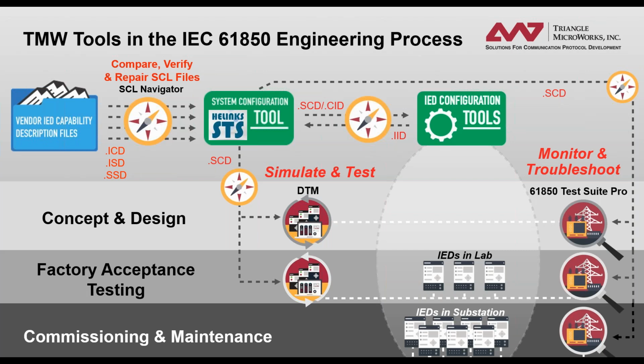I think today a lot of utilities are really aiming to improve their purchase and specification process, so their collaboration with the suppliers. They want to more precisely specify their system in order to get similar solutions for similar substations for maintenance and also for quality. And here, the 61850 process offers the opportunity to make a formalized, standardized specification instead of an Excel-based or Word-based prose specification document.